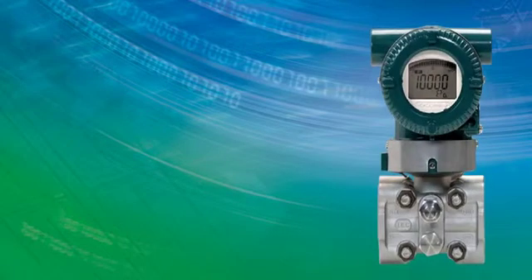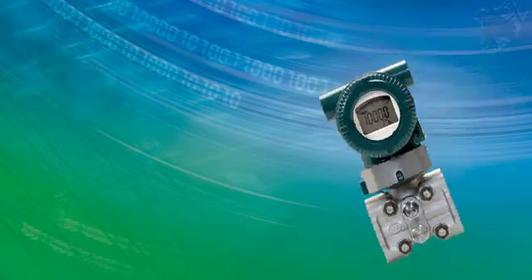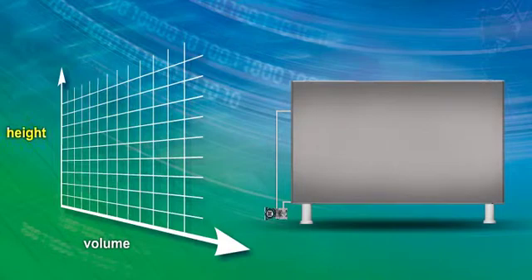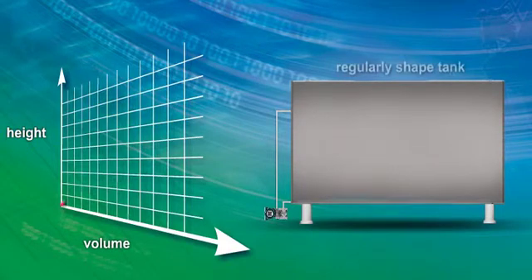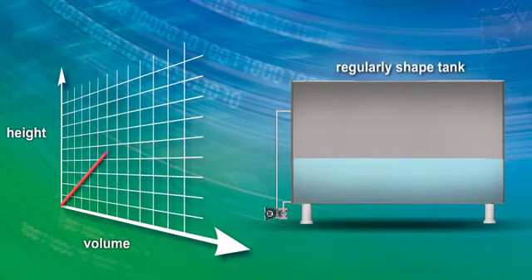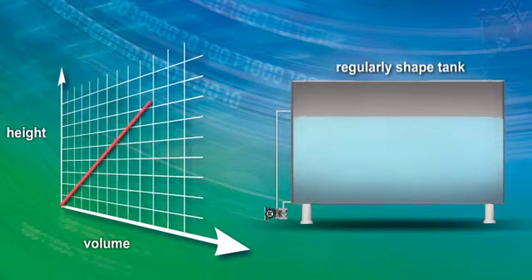A differential pressure transmitter measures level in a tank by measuring the height of the liquid. For regularly shaped tanks, the height is directly proportional to the volume in the tank.